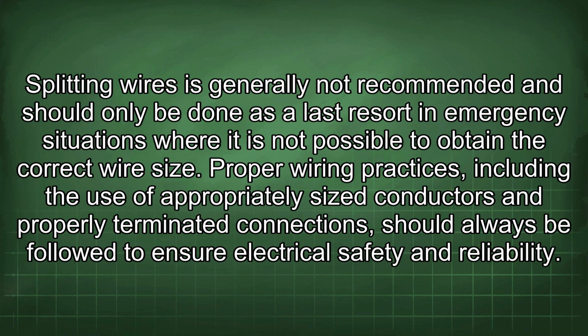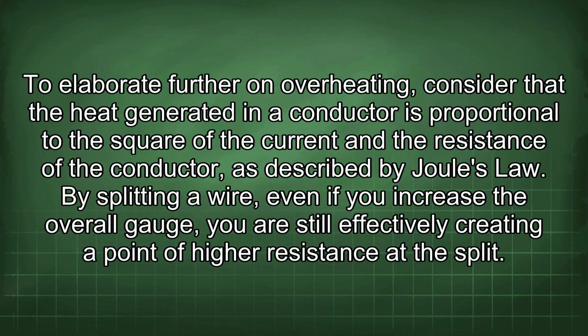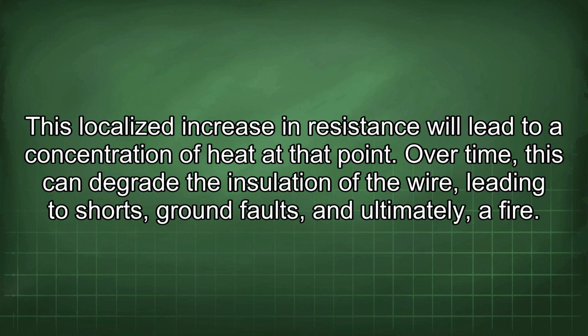electrical safety and reliability. To elaborate further on overheating, consider that the heat generated in a conductor is proportional to the square of the current and the resistance of the conductor, as described by Joule's law. By splitting a wire, even if you increase the overall gauge, you are still effectively creating a point of high resistance at the split. This localized increase in resistance will lead to a concentration of heat at that point. Over time, this can degrade the insulation of the wire, leading to shorts, ground faults, and ultimately a fire.